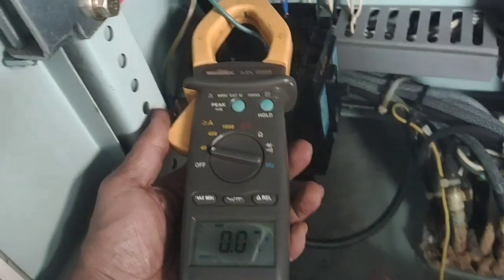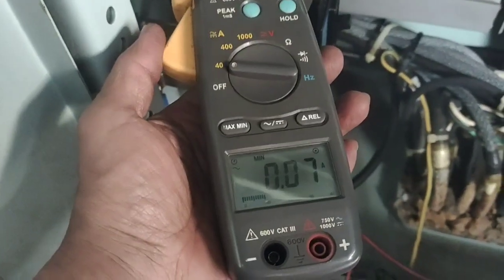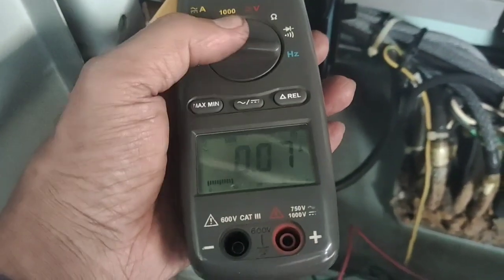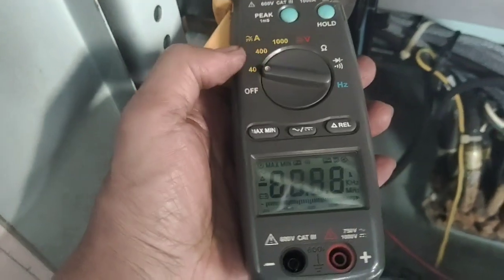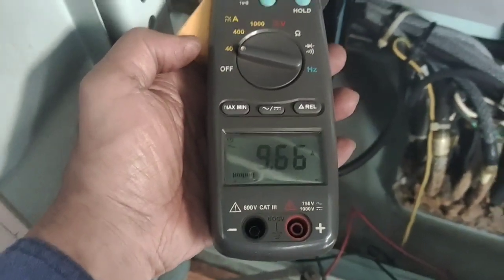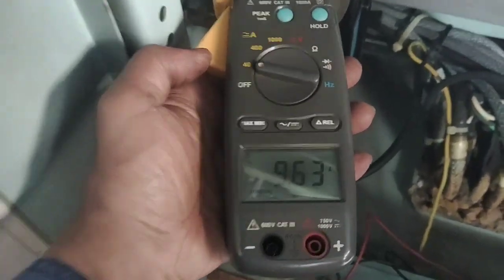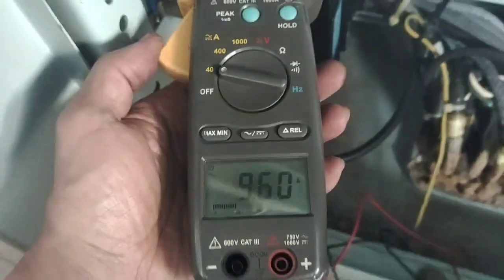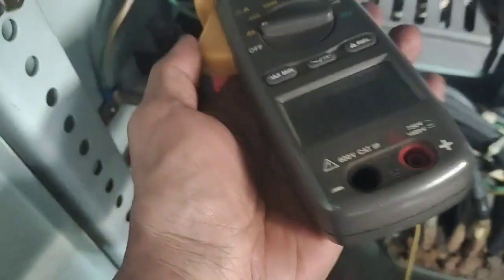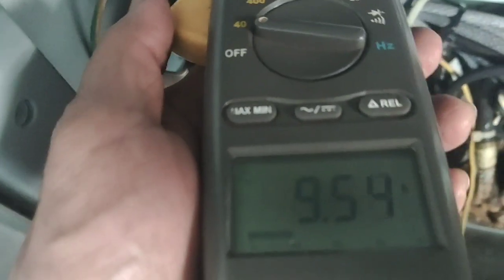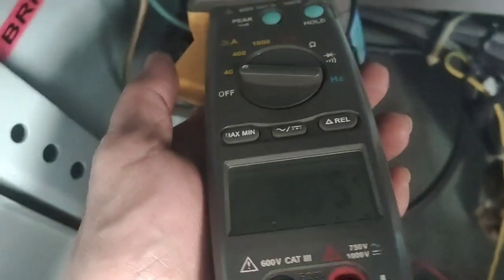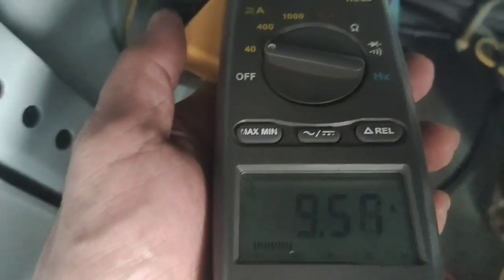And now we will check the current. The current, it has the amperage of this unit, a 5 horsepower air conditioning unit, split type. And we reset. Now we can see it is 9.63, 9.62, 9.61. It's almost 9.6 amps. And we'll see the other side if it's almost the same, or there's a little difference. It's almost the same, almost 9.6. So everything is okay. And thank you so much for listening, for viewing.